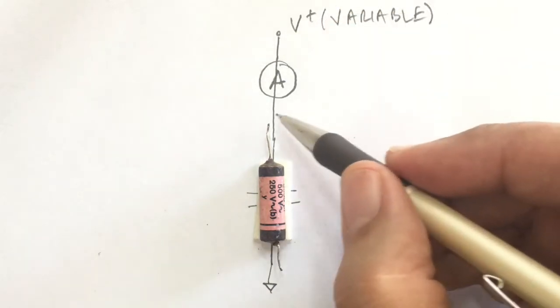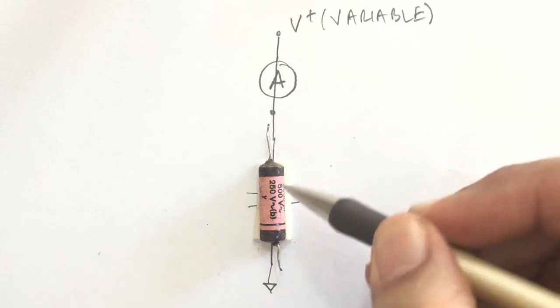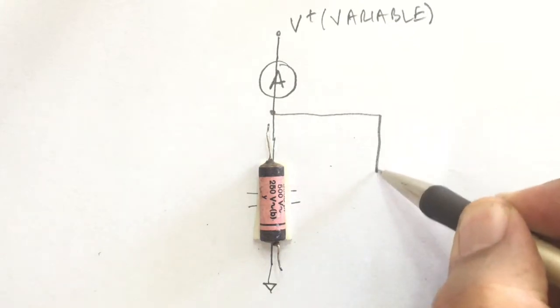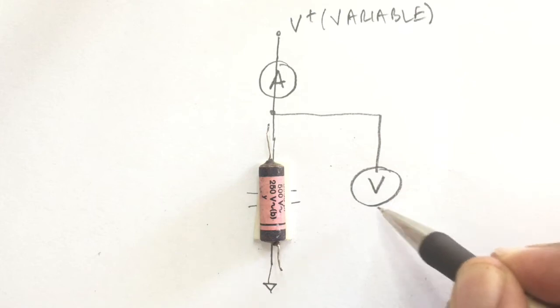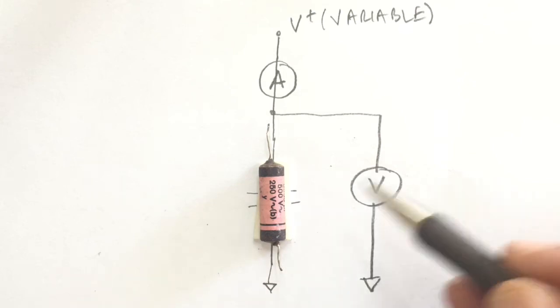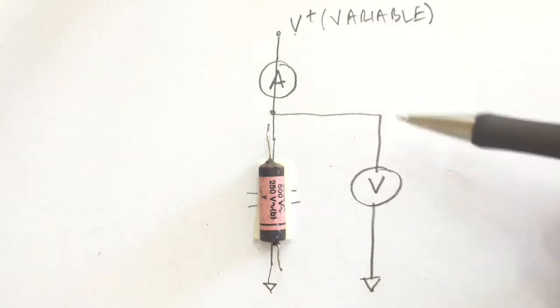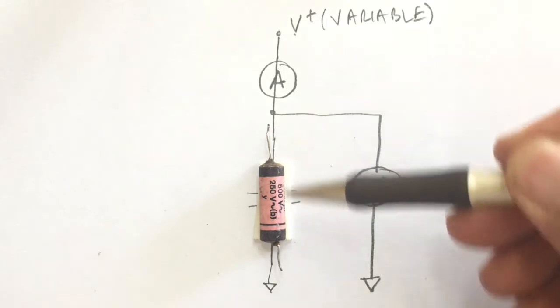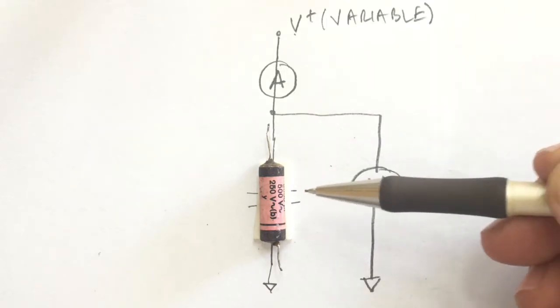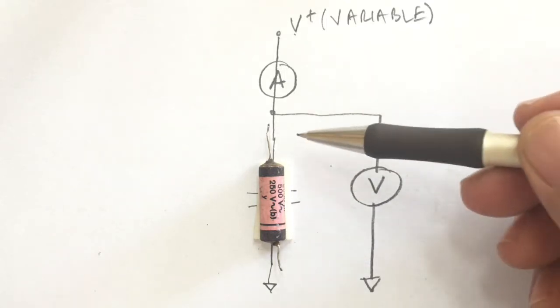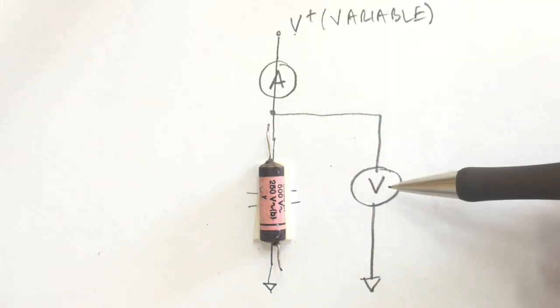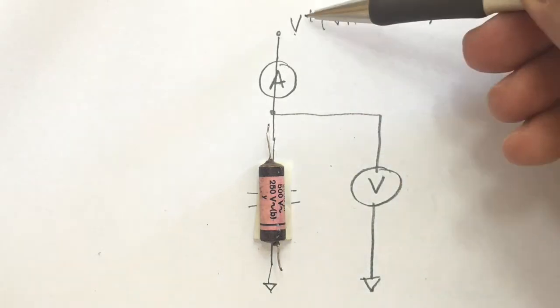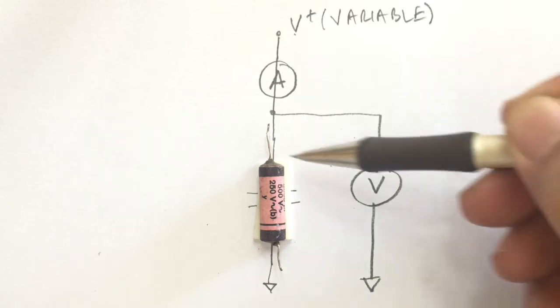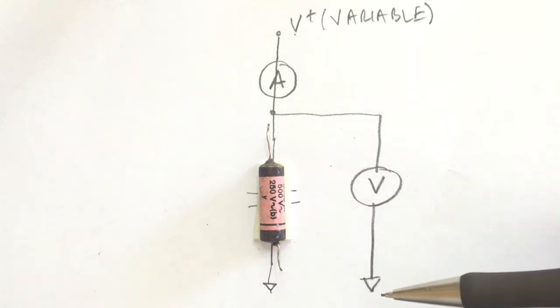The other useful thing is knowing what voltage we're applying to the capacitor at any one time, so we put a voltmeter across there. As we increase the voltage, we can see what's applied across the capacitor. That serves two purposes: it tells us the leakage at a particular voltage, and it helps us increase the voltage to the actual value we want across the cap.